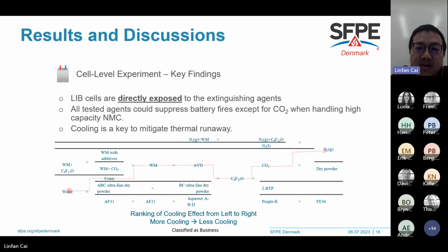Key findings from the cell level experiment: since the battery cells are exposed directly to the extinguishing agents, all tested agents—water-based, gas-based, or powder-based—are able to suppress the battery fires, except for carbon dioxide when handling high capacity NMC batteries. For low capacity NMC batteries, CO2 can still do the job. From the experiments, I also concluded that suppressing the visible fire is not a solution to mitigate thermal runaway.